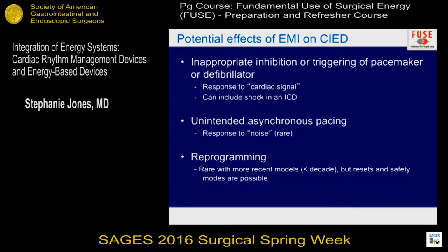There are many potential effects of EMI on the cardiac devices. The most important really to think about is the first one, which is inappropriate inhibition or triggering of pacemaker or defibrillation. Now, most of the new devices are very well shielded, so they can, for the most part, filter out a lot of the noise, but the closer you are to the device, again, the higher the energy, going back to using the lowest energy possible, which almost all our speakers have emphasized, you do have to think about these things. So the pacemaker is going to interpret your surgical energy as a cardiac signal.